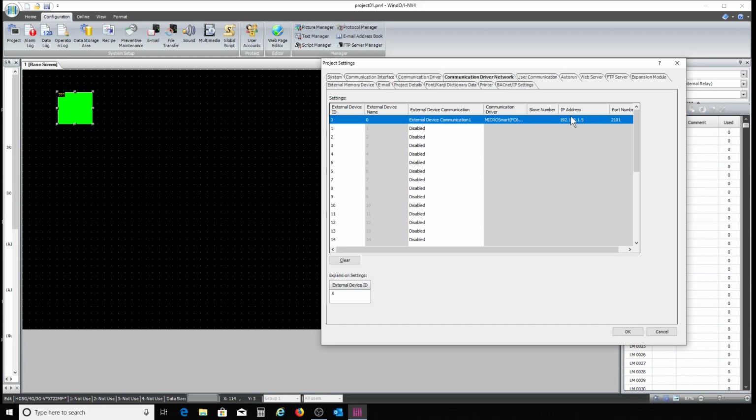And when you click on it somewhere, it's going to pull up and give it this default IP address, which is the default IP address that is set within your PLC unless you change it. This has to match the PLC you're talking to. So you set it in your PLC as something different than your HMI. It can't be on the same .6 as your HMI. It will not work. This last number has to be different. Okay, so we're all good there anyway.